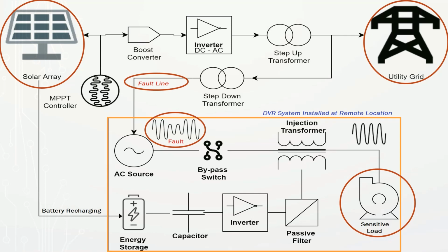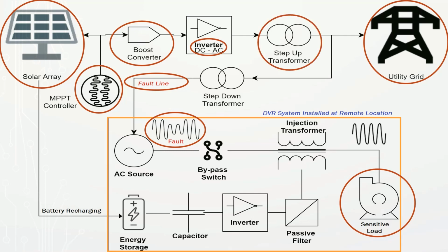In this configuration, a PV array is connected to a boost converter to regulate voltage up to 500 volts by using an MPPT controller. This DC voltage is converted to a low AC voltage level of 260 volts, which is again boosted to AC 25 kV by a step-up transformer to feed the PV generated energy into the utility grid. A second step-down transformer is used between the PV grid and the utility grid network that converts the high voltage level to a low voltage level of 415 volts line-to-line to drive the load.